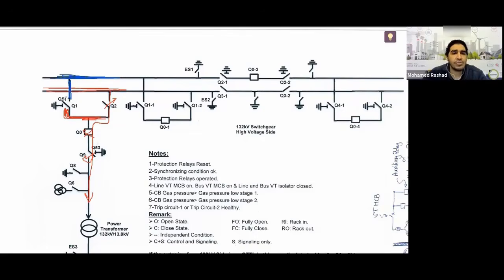All right, he said. In this case, if you want to close this disconnector, what will you do? You must make these two voltages the same. How do you do that? He said, well, you must connect between the two parts, and then close the two parts together. So who is always capable of opening and closing the loads? It's the breaker. That's why I will use the bus coupler.